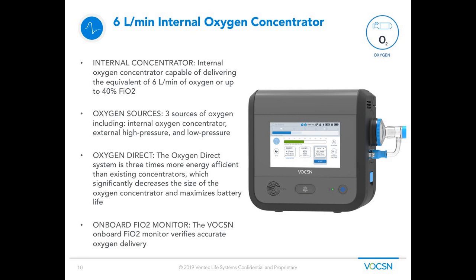One of those benefits is this oxygen direct system where the oxygen and the ventilation are working together, and the front end of every breath is that pure oxygen bolus getting absorbed deep into the lungs where the patient needs it the most, rather than filling up the dead space in the throat and mouth, losing the oxygen in the dead space of the circuit, or out the leak in the exhalation valve. So again, we know exactly how much oxygen we're making because it's one system, and exactly how much oxygen we're delivering to the patient because, again, it's one system and we're doing it on the front end of every inspiratory breath.